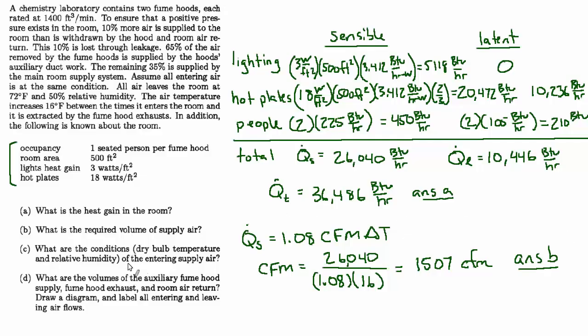They want to know what are the conditions of the entering supply air. Well, we know that the leaving air is 72 degrees and the Delta T is 16 degrees, so it's pretty easy to say what the temperature is. If Delta T is 16, and Delta T is return minus supply, then the supply air is going to be return minus 16, which equals 72 minus 16, so 56 degrees is the temperature of the supply air.